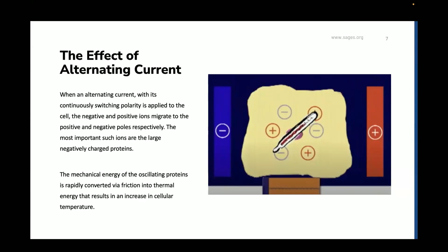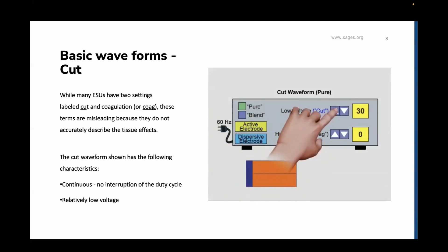There are two basic waveforms that you can adjust through the ESU. We call them cut and coag, although these can be misleading terms. Essentially, cut allows you to deliver a continuous, non-interrupted current through your active electrode that is low voltage.